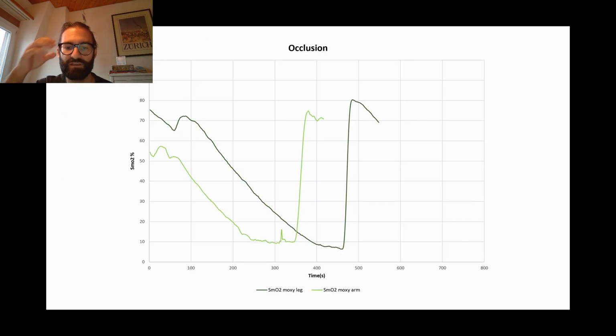So this is an occlusion with the Moxy on my leg and on my arm. You get this downward trend in both of them. You see you reach some kind of minimum value, and then you get this hyperemia response back up. This pattern is what you should see in the NIRS device. If you don't have this pattern, this fall, this plateau, and this increase up higher, your NIRS device is probably not measuring correctly. So that's step one.